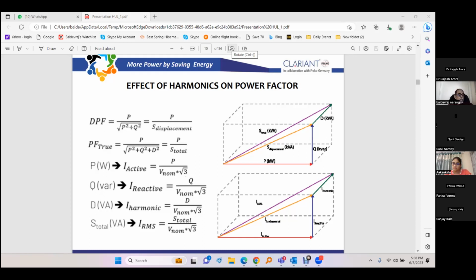So we are trying to have a blanket requirement as far as capacity, the kVAR, as well as the type are concerned. We found that all these things should be looked into before we make anything mandatory. Earlier, the switched capacitor banks or shunt reactors were not automated. They were only fixed banks, and they could not follow the load pattern.